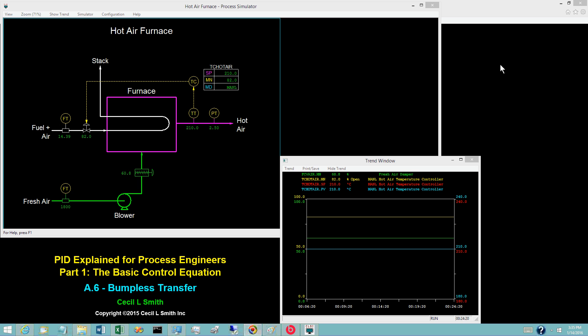In a production facility, transitions from one mode of operation to another must be smooth or bumpless. This applies to transitions between the manual and auto modes for the PID block. Achieving a bumpless transition from auto to manual is easy — the controller output in manual must equal the controller output in automatic just prior to the switch. Achieving a bumpless transition from manual to auto requires that the computations be initialized properly, specifically by computing the initial value for the controller output bias. These computations are described in this video.